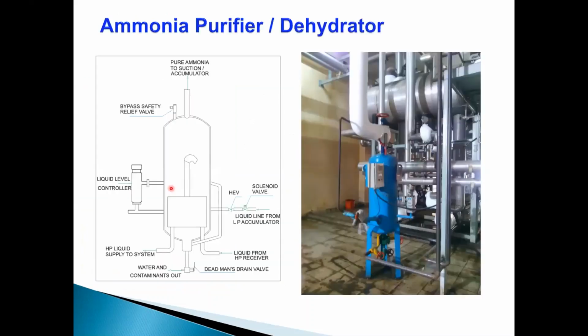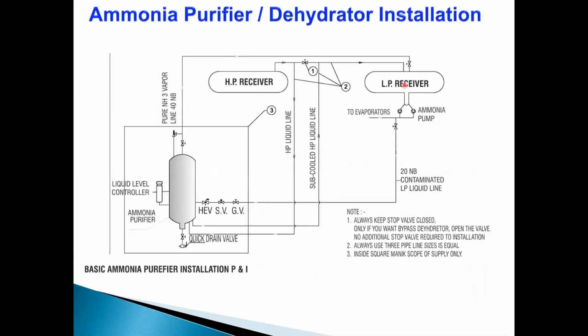What we can do is have an ammonia dehydrator. An ammonia dehydrator is a device which removes water, oil, and dirt from the refrigeration plant, and lets you use pure ammonia continuously, online. This can be installed in a running plant, which saves a lot of energy. What we have here is that we use heat from the high pressure receiver, spread through a coil into this, and it is taken back into the liquid line.